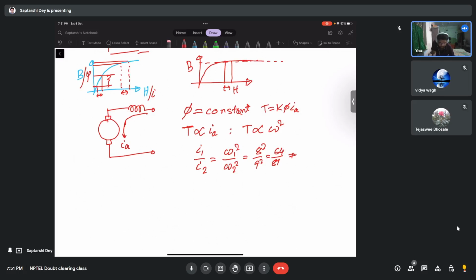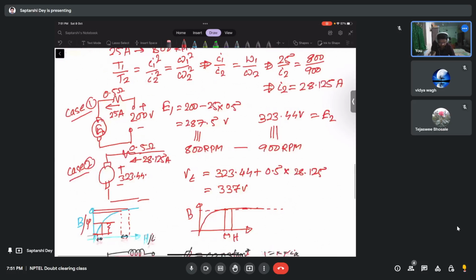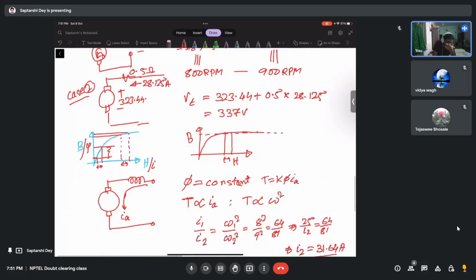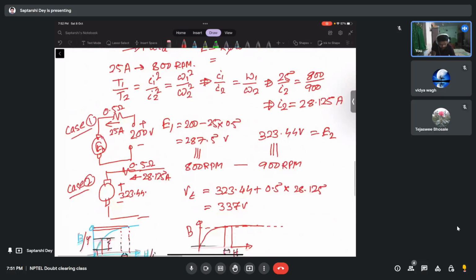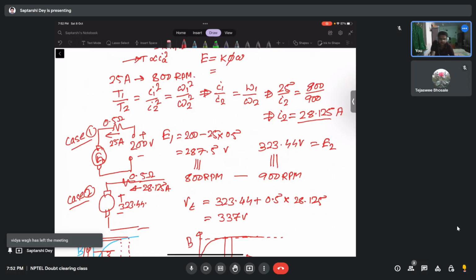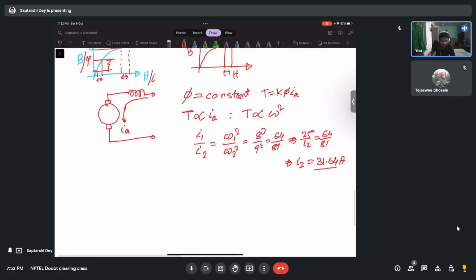So what is I1 by I2? 25 by I2 is 64 by 81. So we have I2 equals 25 times 81 by 64, which comes out to be 31.64 ampere. So you see it is 31.64 ampere now. Previously, to run the fan load at the same speed, the required current was 28 ampere. So with increasing saturation of the system, we need more current. More current in a saturated system. It is very practical.